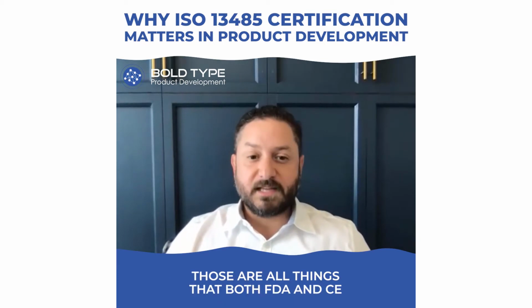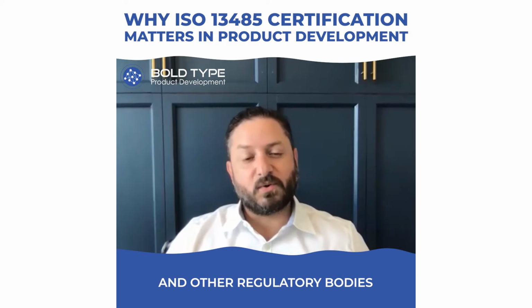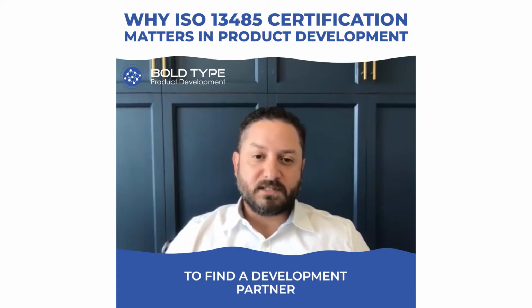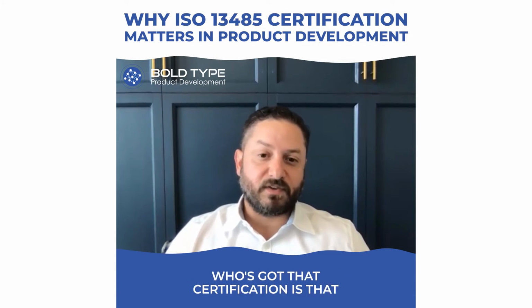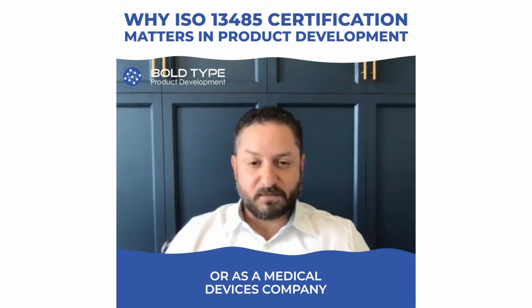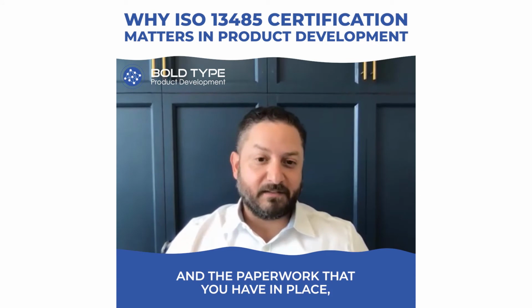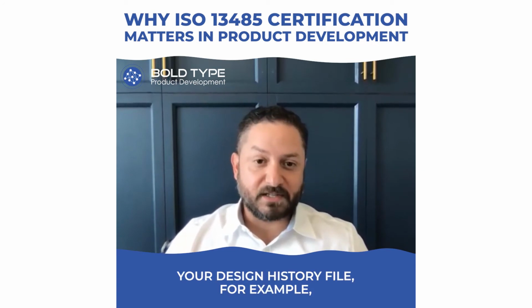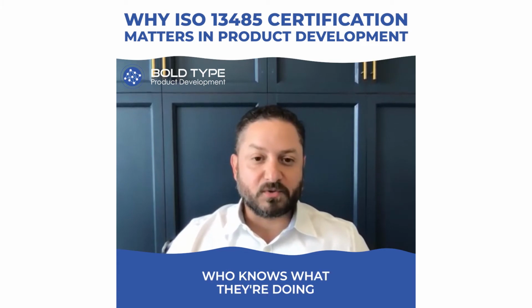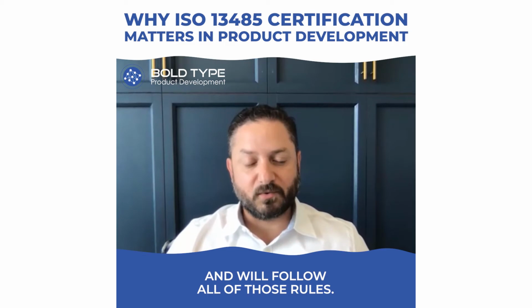So those are all things that both FDA and CE and other regulatory bodies will want to see a company doing. And the reason it's important to find a development partner who's got that certification is that it reduces the risk on your end as an OEM or as a medical devices company that someday you'll be audited by FDA and the paperwork that you have in place, your design history file, for example, will not be in order. So you want to work with a partner who knows what they're doing for medical device product development and will follow all those rules.